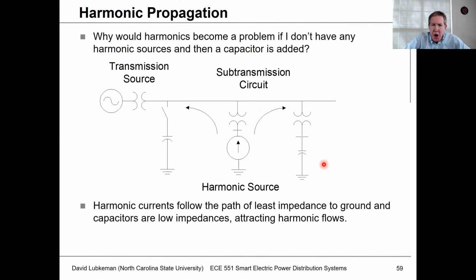As far as harmonics propagating in distribution circuits, let's suppose we had a harmonic source inject current. Where does it go? Well, it's kind of like lightning in a way. It basically looks for a path to ground. It looks for the low impedance path to ground. And what would cause a low impedance path to ground? Well, normally we're going to have low impedance paths to ground through capacitors, because the combination of a line reactance in series with a capacitance, usually those are going to interact in such a way that those capacitors are going to make kind of low impedance paths to ground possible.